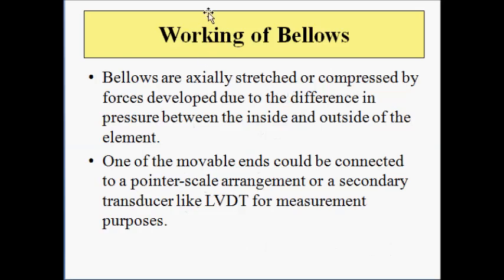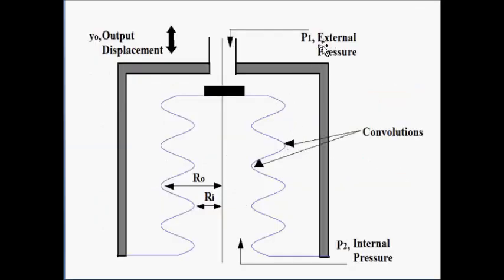Now the working of bellows. We get an output in terms of a mechanical displacement which gives the value of the pressure or force. Because of the differential pressure between the inside and outside of the bellow, they are axially stretched or compressed — either expanded or compressed along the axis. There are two cases: either the external pressure is greater than the internal pressure, or the internal pressure is greater than the external pressure.